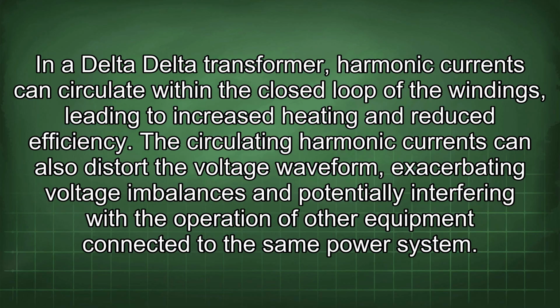In a Delta-Delta transformer, harmonic currents can circulate within the closed loop of the windings, leading to increased heating and reduced efficiency. The circulating harmonic currents can also distort the voltage waveform, exacerbating voltage imbalances and potentially interfering with the operation of other equipment connected to the same power system.